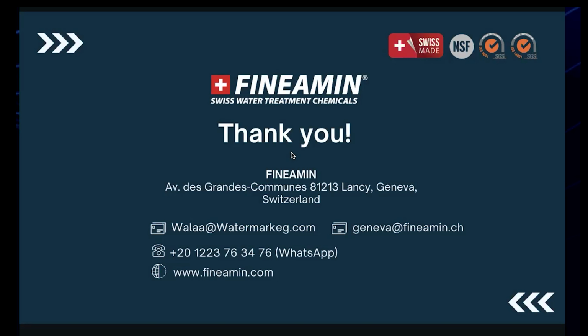And we can measure this during our treatment with Fineamin till it vanished from the system, and we are sure that there is no phosphate in the system and everything went smoothly. No problem for this, no specific preparation just to shift from the old treatment to Fineamin. It went very smoothly with them. That's all that happened.